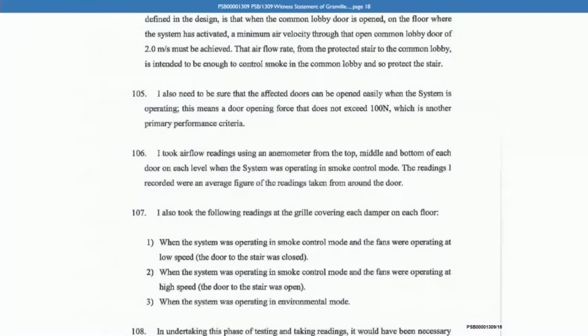Yes, that's helpful. Can I just look at what you said in your witness statements about this? If we could go to paragraph 106 of your first statement at page 18. You say here in this part of your statement, I took airflow readings using an anemometer, from the top, middle and bottom of each door on each level when the system was operating in smoke control mode. The readings I recorded were an average figure of the readings taken from around the door. Now, do you see that written like that? It sounds like you've just taken 3 readings, top, middle, bottom.